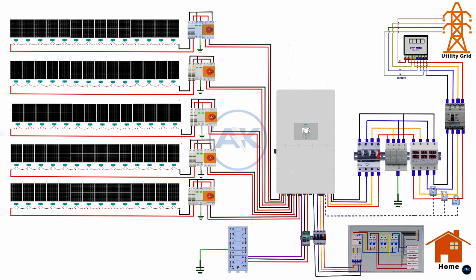Step 8. Grounding and final checks. Now we complete grounding and perform final checks before powering on the system. Proper grounding is essential for safety, equipment protection, and correct operation of the inverter, batteries, and surge protection devices. Start with the main grounding system. Install a dedicated earth electrode or grounding rod according to local electrical standards. This ground point will be the reference for the entire solar system.